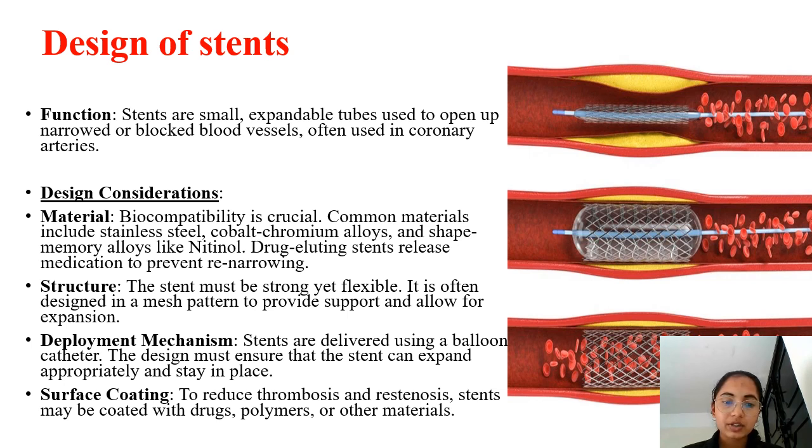Deployment mechanism. Stents are delivered using a balloon catheter. The design must ensure that the stent can expand appropriately and stay in place. So next is surface coating. To reduce thrombosis and restenosis, stents may be coated with drugs, polymers, or other materials.